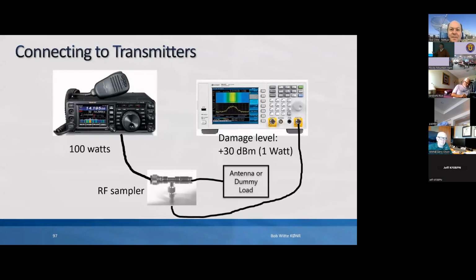That's really good. One thing I noticed over the years is that high quality spectrum analyzers, signal generators and such, they do what they can to make them robust and not blow up easily, but you can blow them up. The service monitors, something they know is going to be connected to a transceiver, they usually put more protection in, relays that open and stuff, trying to save that poor device from the mistake of the operator.